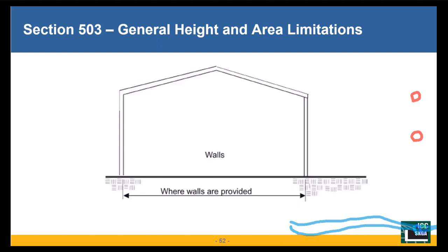And again, that factor in the table, or the pure area, is just per story, and it does not include any increases. However, when we get to the table, we're going to see the difference between sprinklered building allowable area and non-sprinklered building. And we can see the increase is already built in for that in that table for a sprinklered building.